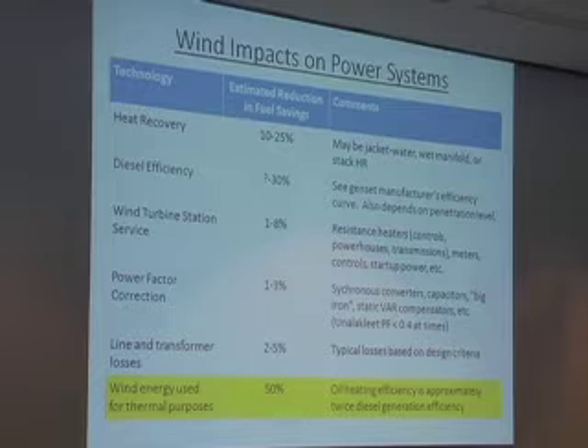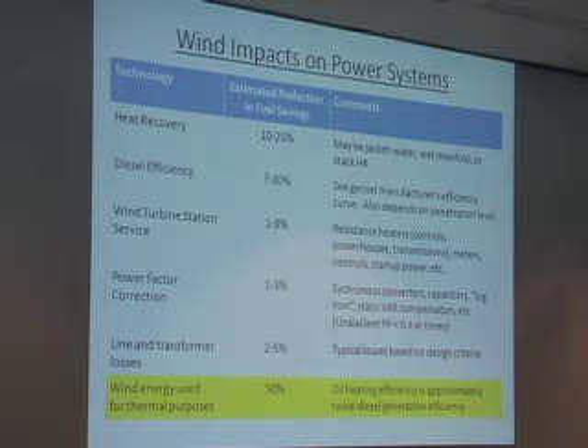Station service, I don't have a lot of good data on this. I'd appreciate it if somebody in the audience does. It's not even clear sometimes whether there's a station service meter on the wind turbines themselves. But this is a range that we've seen some indication of, 1 to 8%, and it goes for things like resistance heaters to keep the controls warm and reduce condensation and impacts on the controls, warm transmissions where there is a transmission, meters, and then startup power as well.